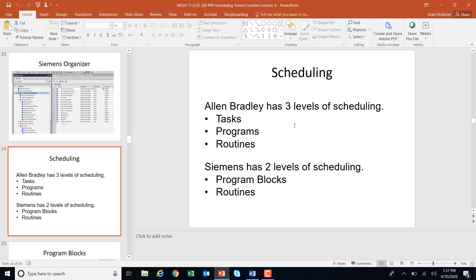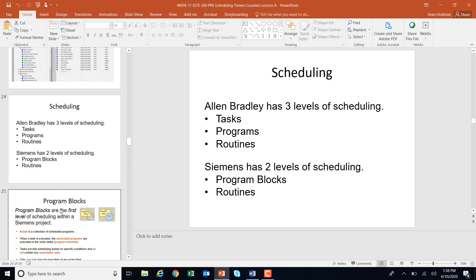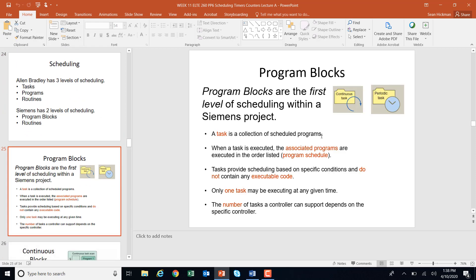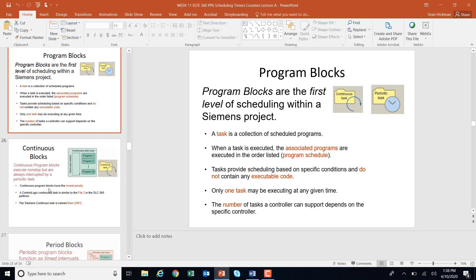Allen-Bradley has three levels of scheduling: tasks, programs, and routines. Siemens has two levels: program blocks and routines. We've been working with our main OB and scheduling routines into it. In these program blocks, you can schedule either with continuous scheduling or periodic scheduling. Up to this point, all we've been doing is continuous scheduling — when we take the main OB, it's always scheduled, and any subroutine in it is always scanned. But there are periodic tasks that occur every once in a while — that's another form of scheduling. Continuous tasks have the lowest priority; they're always running but can be interrupted by something with higher priority.